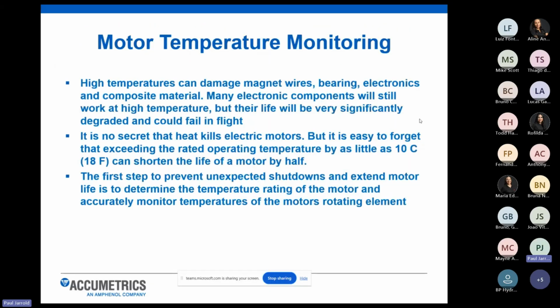High temperatures can cause significant damage to the wiring, the bearings, electronics, and any kind of composite material inside of motors. Monitoring temperature is one of the best ways to predict failure, because if you're driving this motor beyond what it was designed to do, or you're driving it longer, you can create an excess amount of heat inside of the motor, inside of the armature windings. And over time, that heat can cause damage to your machine. This is just an example that a rise of 10 degrees C can shorten the life of your motor by half.